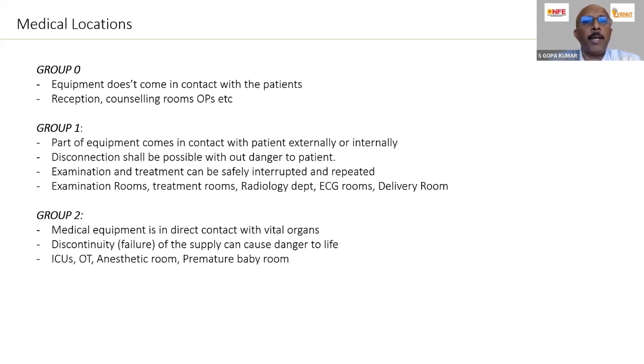Some biomedical equipment is sometimes connected or used for some kind of checking and so on. So in a group 1 location, disconnection shall be possible. That means even if the power supply disconnects, there is no big danger. Some examples are the examination room, treatment room, and so on. We have a chart we will show you later.